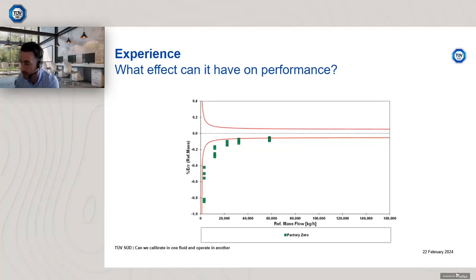So they'll have a factory zero. This should be published in the certificate you get when you purchase the device. And you can see here, I've manually inserted the factory zero back into this device rather than creating a new zero value when it's been installed. And you can see the results are slightly out of specification, suggesting that the factory zero is different from what the meter zero should be in service.